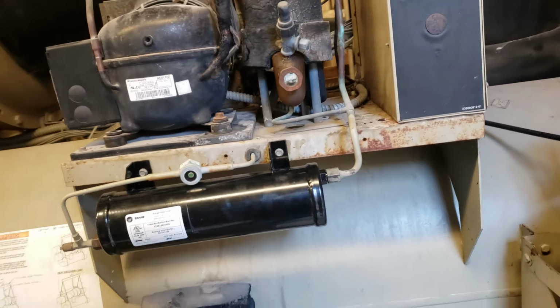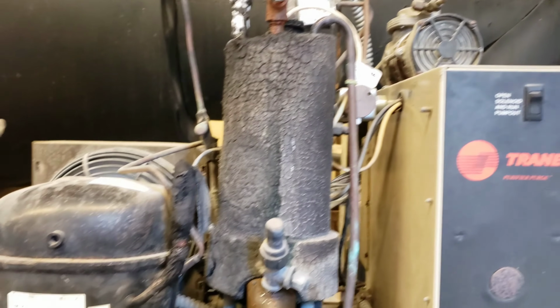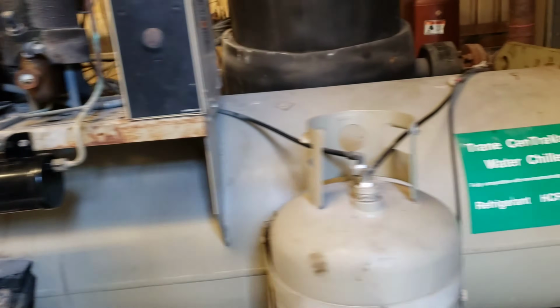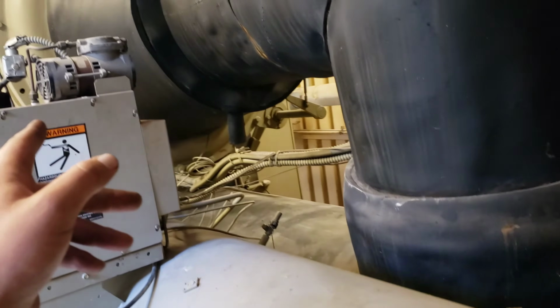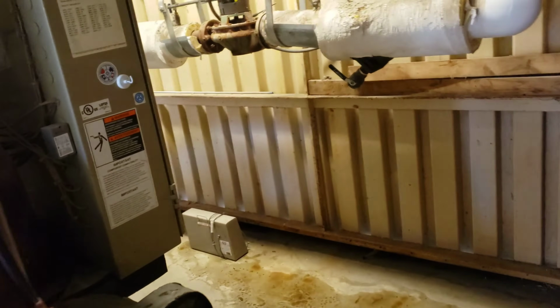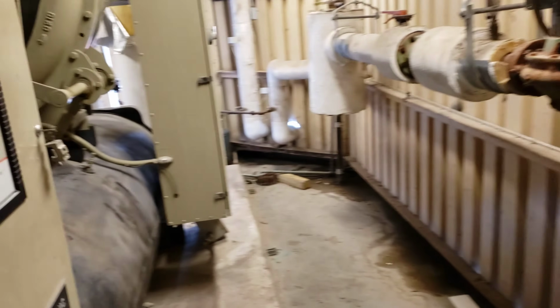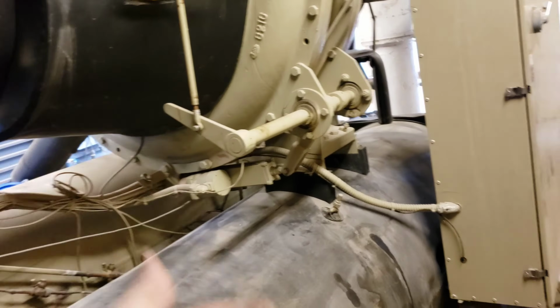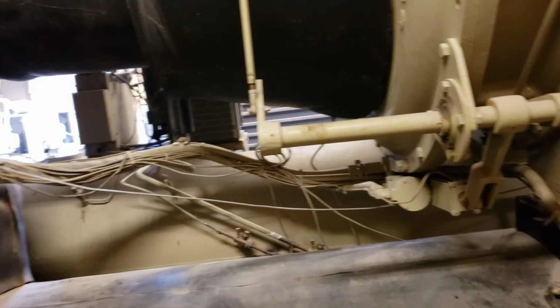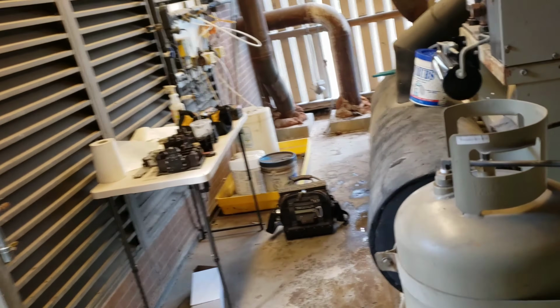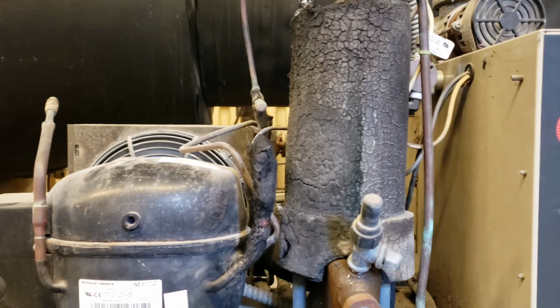So the most impactful thing it did was it did not allow the purge system to operate properly, because the pump out on the purge operates off of an algorithm inside of the micro panel system. Well, that algorithm looks at condenser saturation temp for one of its primary numbers to know if it's good or not. And so it's looking at that temp, and it's also looking at the compressor suction temp on the purge machine. Anyway, due to that, it never realized that it needed to purge at all. It always thought that it was within range and it had no atmosphere in the system, which was completely false. That was the cause of my surging.